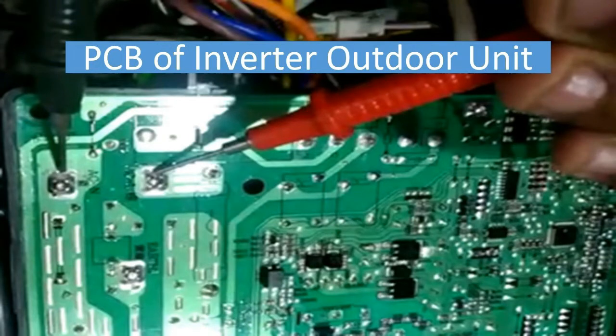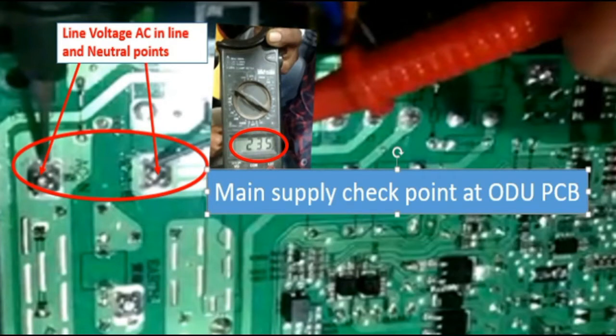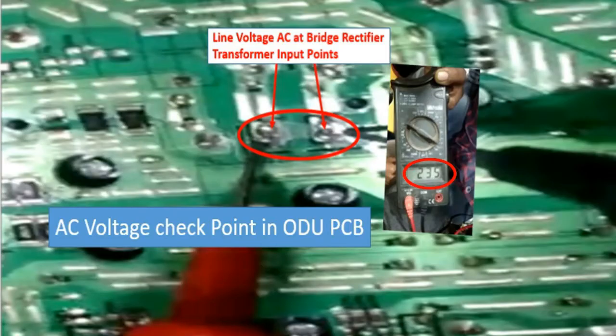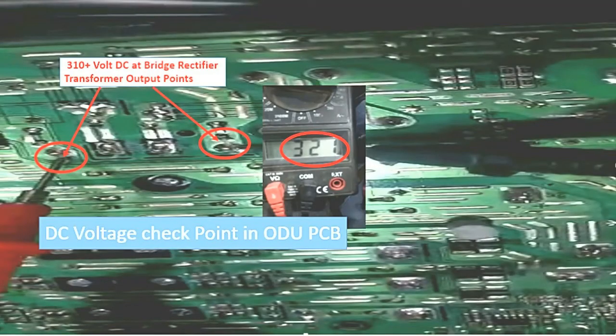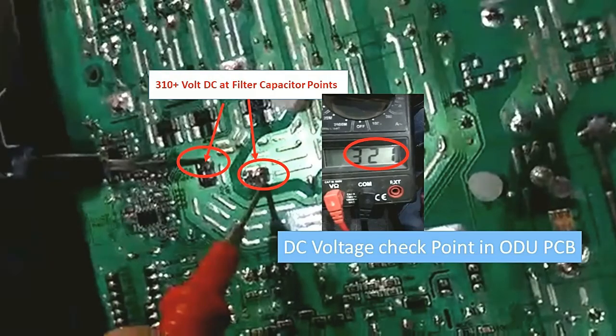To check further, in the ODU PCB, between neutral and line wire, we have to get the AC line voltage. Next, in the bridge rectifier, between the input points, which is shown here, we will get the line voltage, and in the output terminals we will get the DC voltage, which should be 310 or more. If it is available, then the bridge rectifier is okay. For checking the filter capacitor, we have to measure the DC voltage between the minus and plus points of the capacitor. It has to be again more than 310 volt DC.